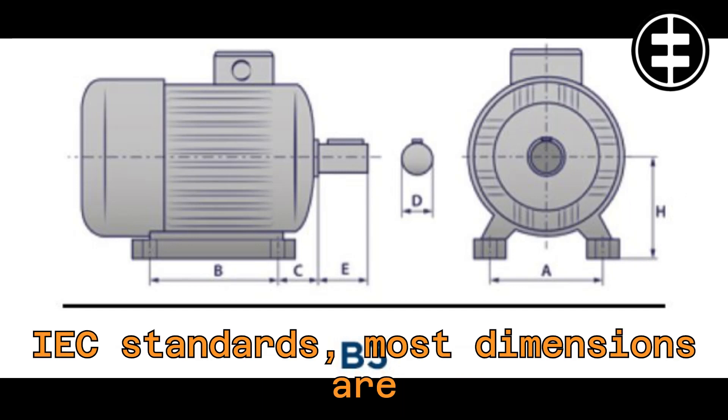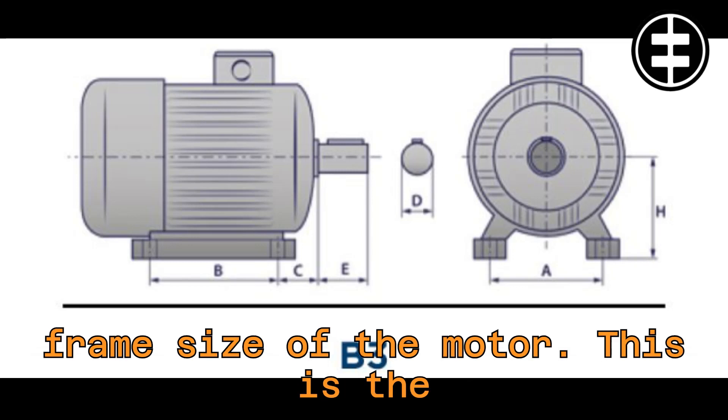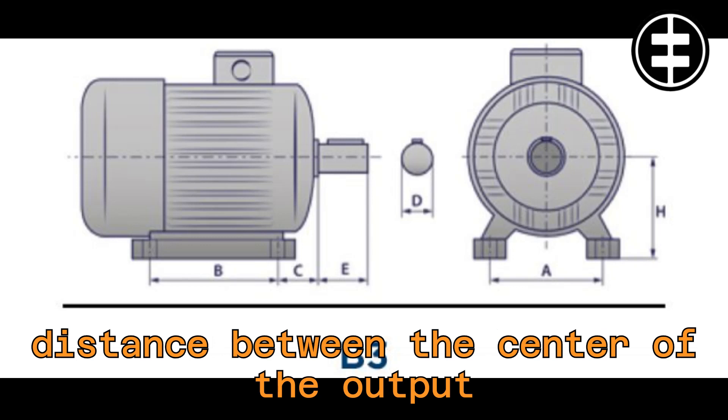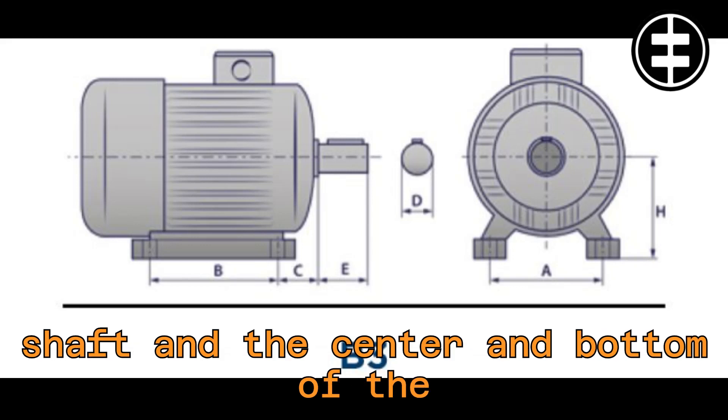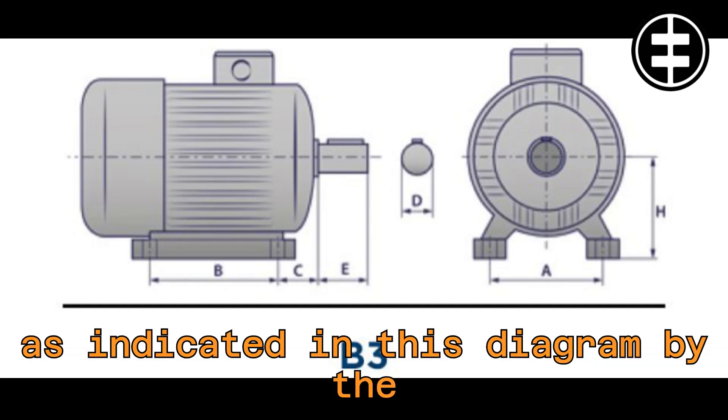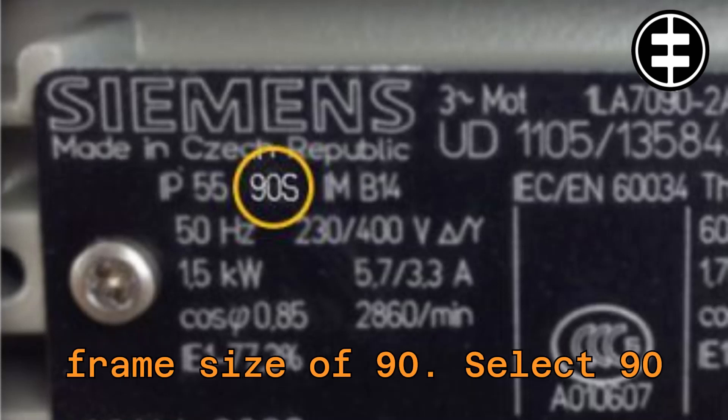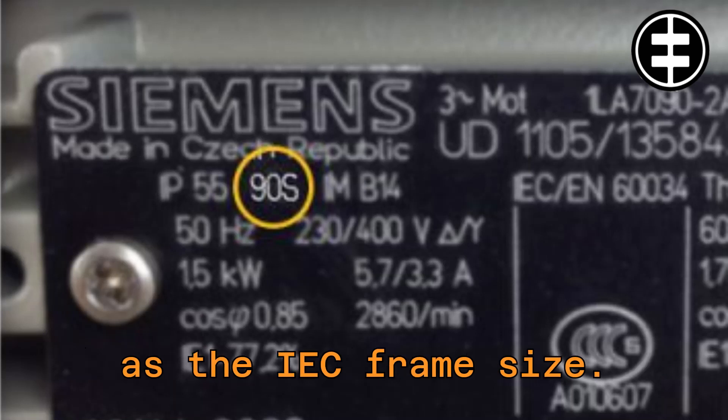For electric motors adhering to IEC standards, most dimensions are directly related to the shaft height or frame size of the motor. This is the distance between the center of the output shaft and the center and bottom of the feet of a B3 style motor, as indicated in this diagram by the letter H. In our example, the electric motor has a frame size of 90. Select 90 as the IEC frame size.